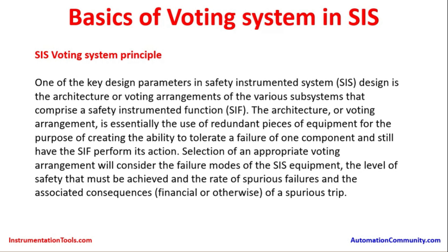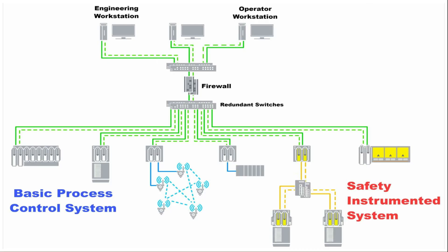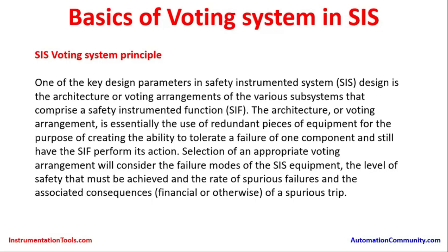One of the key design parameters in safety instrumented system design is the architecture or voting arrangements of the various subsystems that comprise a safety instrumented function. The architecture or voting arrangement is essentially the use of redundant pieces of equipment for the purpose of creating the ability to tolerate a failure of one component and still have the SIF perform its actions.